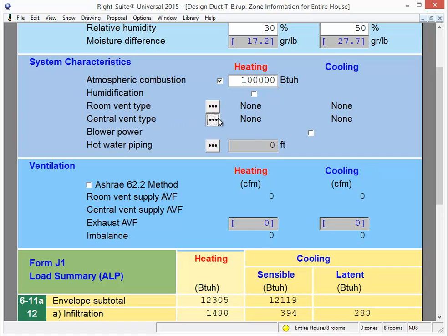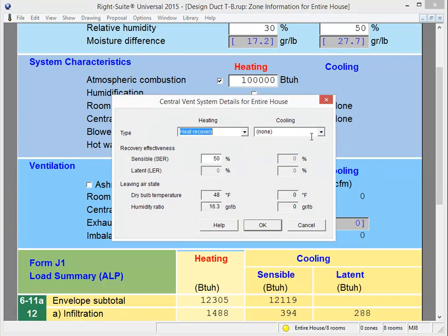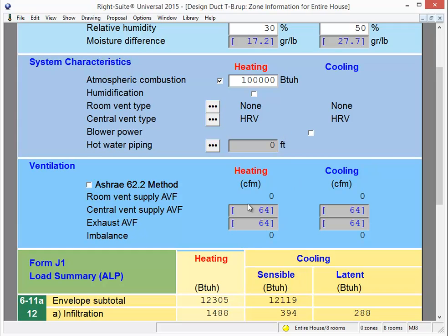So if I choose as my central vent type — let's say I'm going to use an HRV — I select my HRV and set the sensible effectiveness. This is not a default value in the sense that we're recommending 50; this is going to depend on the unit, and I'm going to look that up from the technical data. When I click OK, the program populates a ventilation number. This ventilation number is by default based on Manual J's recommendation for ventilation, which is just that — a recommendation, not a requirement. Whereas in many situations, ASHRAE 62.2 is required by local code. Prior to this, you could use external tools to determine your ASHRAE 62 ventilation and override the fields here in Right-Suite.